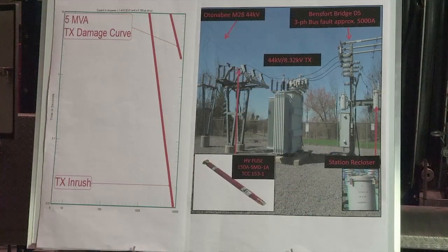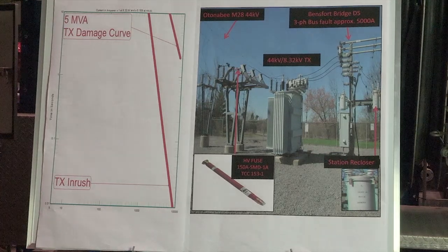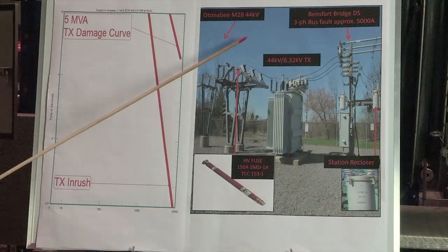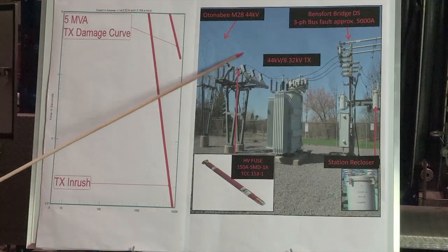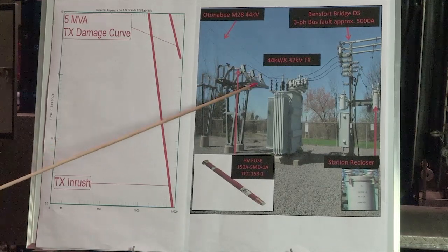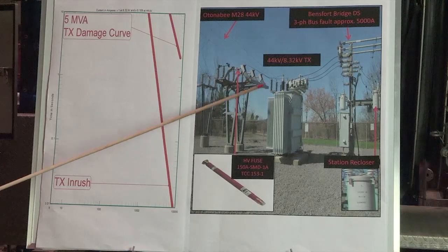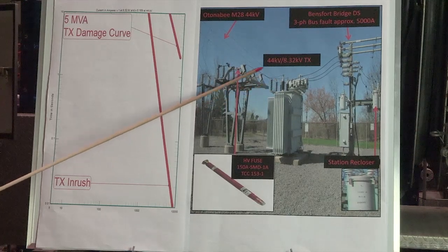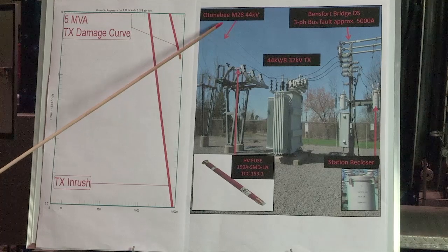Now, with the diagrams beside me, I'm going to be going over how we set protection and coordination with all the devices upstream and downstream from the TS. Starting with the diagrams beside me, I'm going to be going over protection from the 44 kV line, which is M28 44 kV, to Bensfort Bridge DS. Now, starting with the transmission station, we have the 44 kV line.